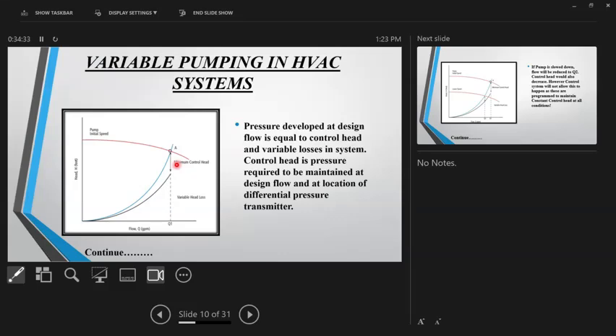How do you control the speed of variable pumping? Is by a delta P sensor, correct? You would put a pressure differential sensor or delta P transmitter at, say, a further circuit somewhere. Some people put it at two-thirds, some people put it at the most important AHU. So the pump speed is basically controlled to maintain that delta P constant, right? So the differential pressure transmitter or DP transmitter decides the speed of the pump.